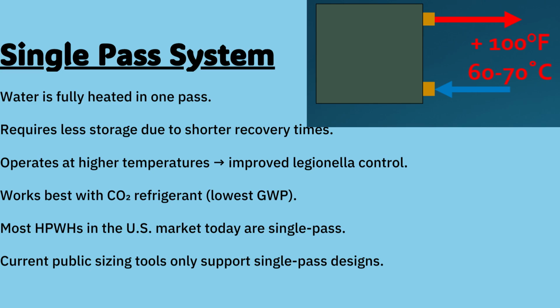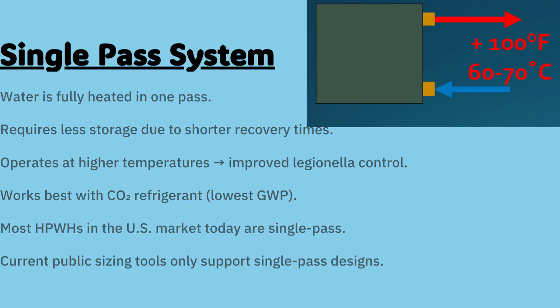They also operate at higher temperatures, which improves control of Legionella bacteria. And because many single-pass systems use CO2 refrigerant, the lowest global warming potential refrigerant available, they're an environmentally friendly choice. It's no surprise that most heat pump water heaters on the market today are single-pass. In fact, all the publicly available design tools for sizing currently only support single-pass designs.